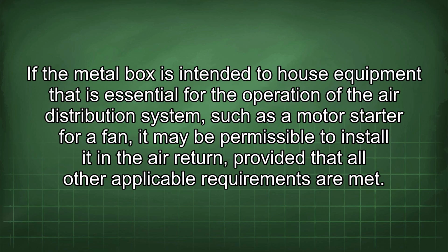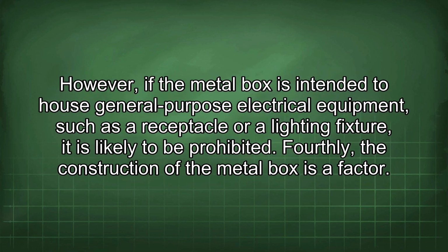If the metal box is intended to house equipment that is essential for the operation of the air distribution system, such as a motor starter for a fan, it may be permissible to install it in the air return, provided that all other applicable requirements are met. However, if the metal box is intended to house general-purpose electrical equipment, such as a receptacle or a lighting fixture, it is likely to be prohibited.